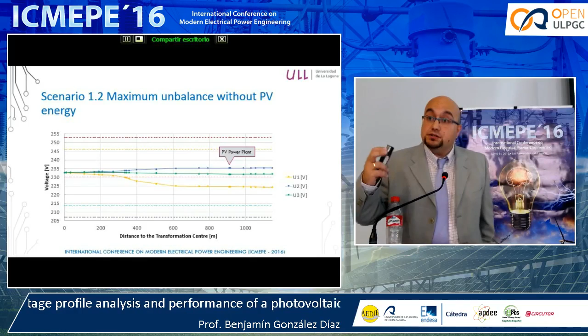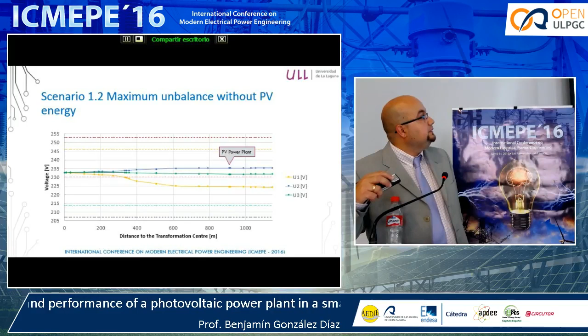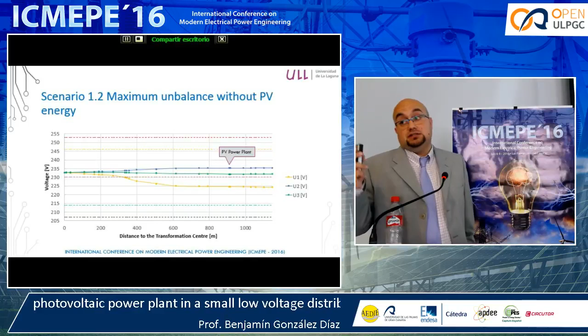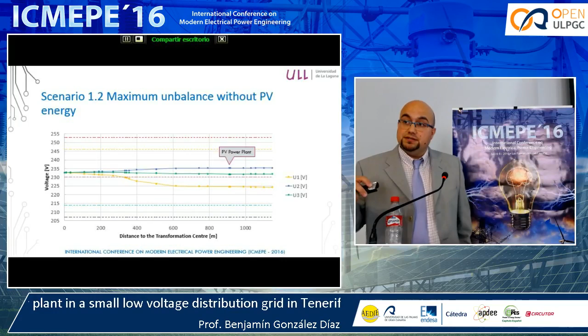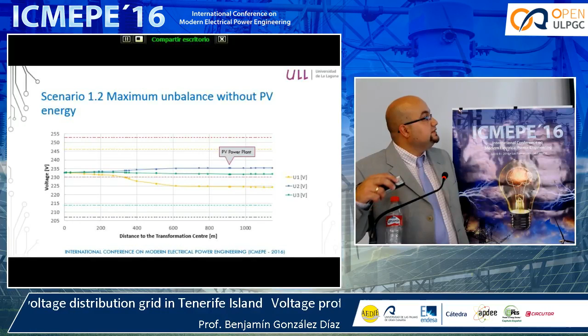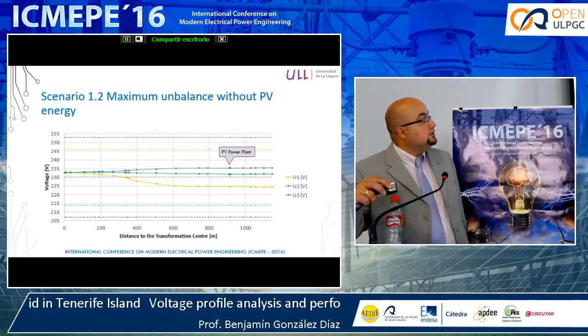There isn't any problem with the voltage in the line. We can see through the line we are keeping more or less the same level, which means there aren't too many customers connected to line 2. In line 1, there are plenty of customers, so we are here at 230, placed more or less exactly in the middle, between the upper limit and the lower limit.